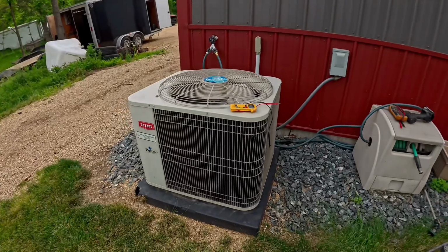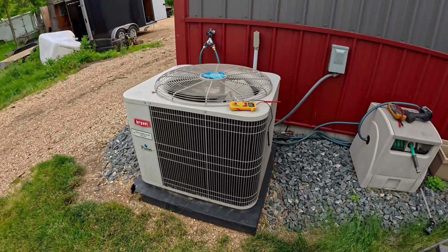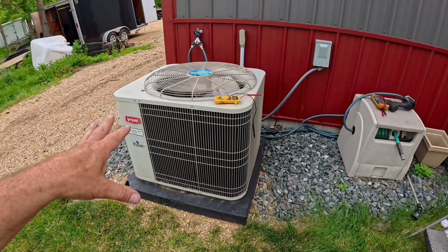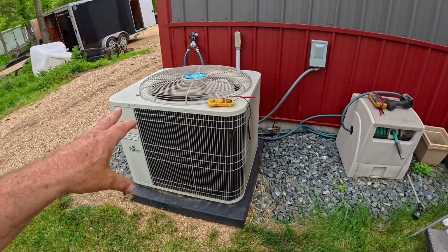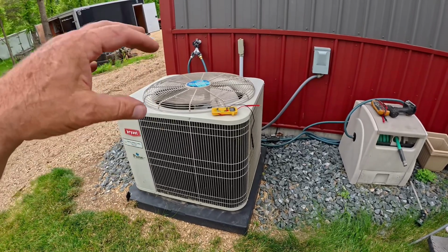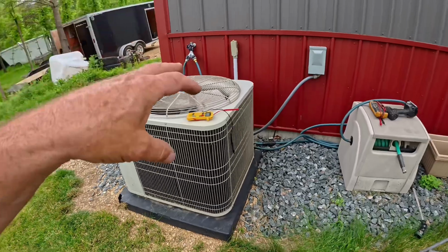All right, so now let's run through the most common scenario. You come home, it's hot in the house, the fan is in fact running in the indoor unit, the filter's fine, no signs of trouble, so you come outside and nothing. The outdoor unit is not running. This is the most common scenario in an HVAC service call. So we're going to go over the basics of what you can do to try to get through this problem.